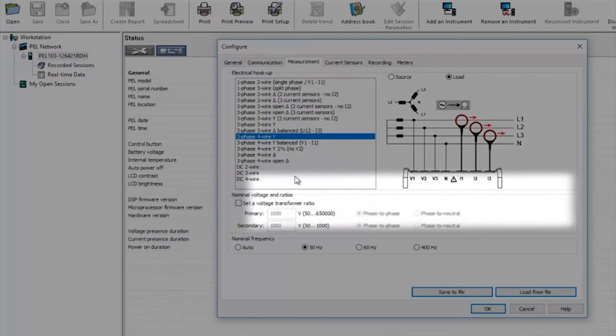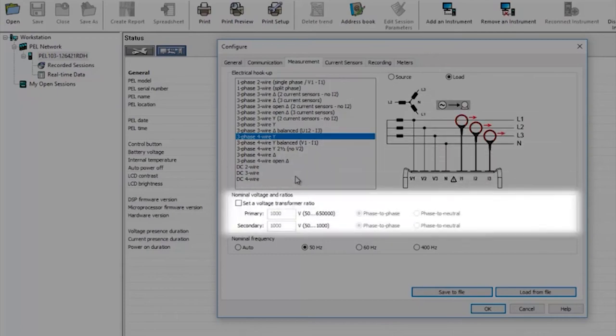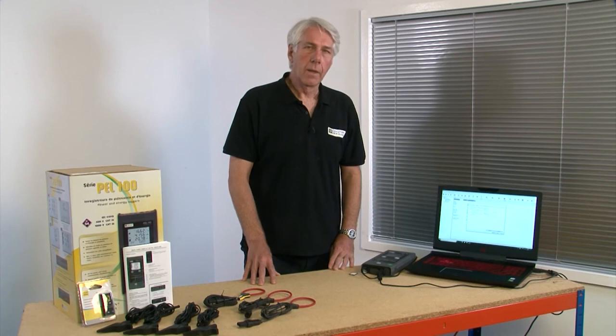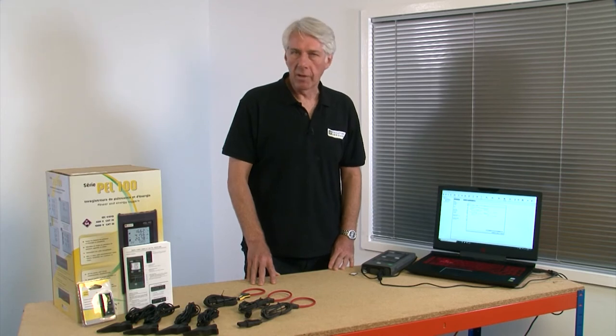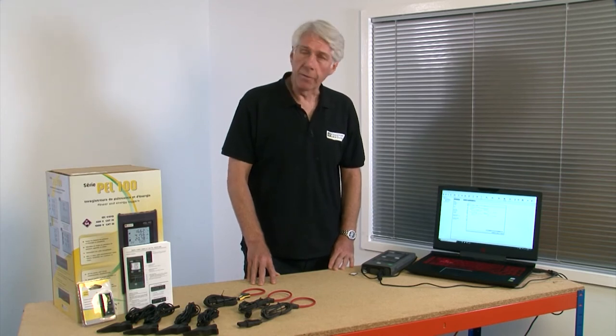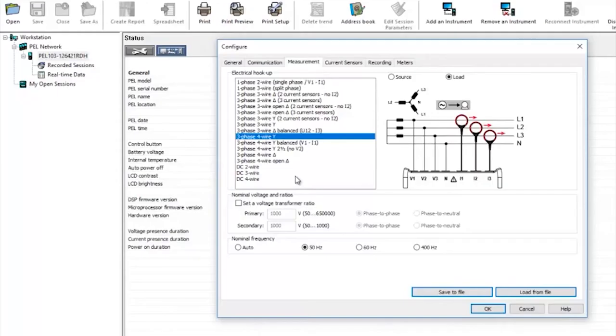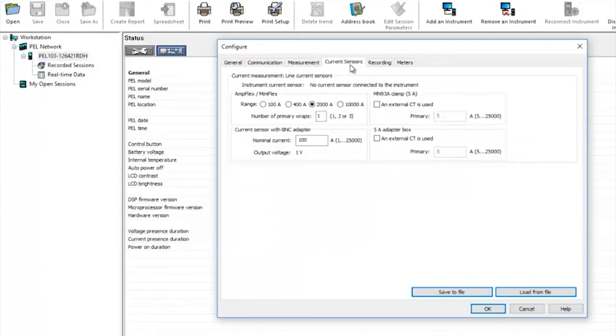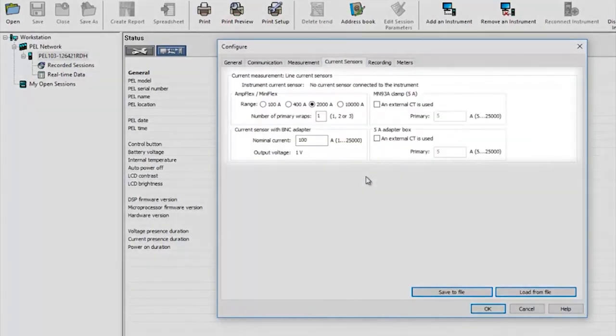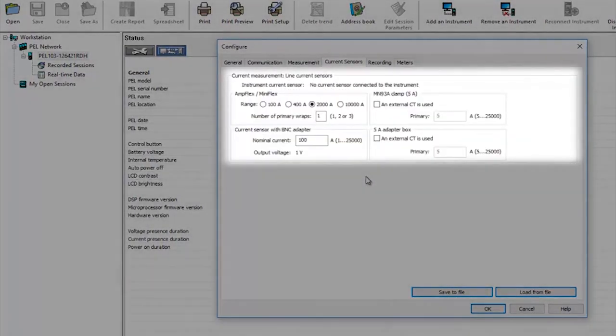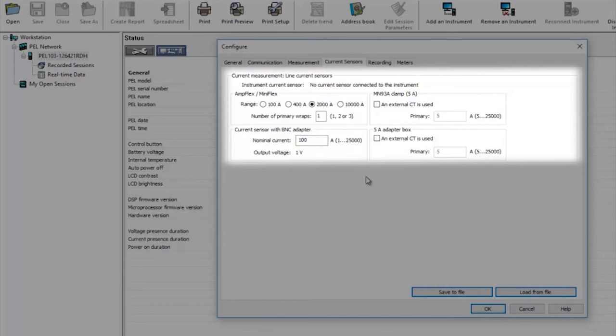In this section you can set up voltage transformer ratios in the event that you're connecting to a high voltage supply through a VT or voltage transformer. There are a number of current sensors available for the PEL to suit different requirements. As with previous VT settings it's also possible to set a current transformer or CT ratio in the event that you're connecting to high current networks through CTs. If you're connecting to CTs within the installation you can either connect directly to them or will need to use MN93A clamps and enter the ratio of the CT clamp you're connecting to here.